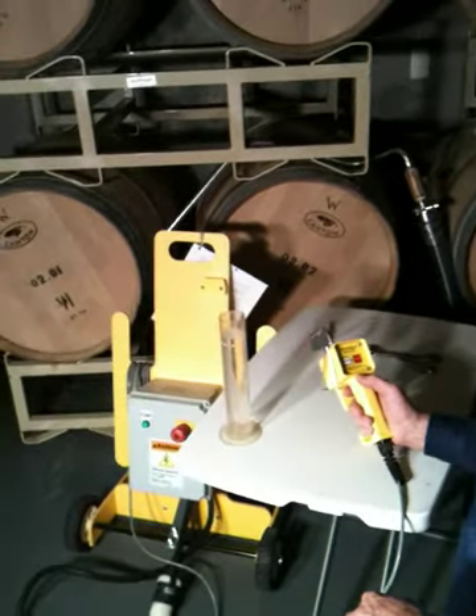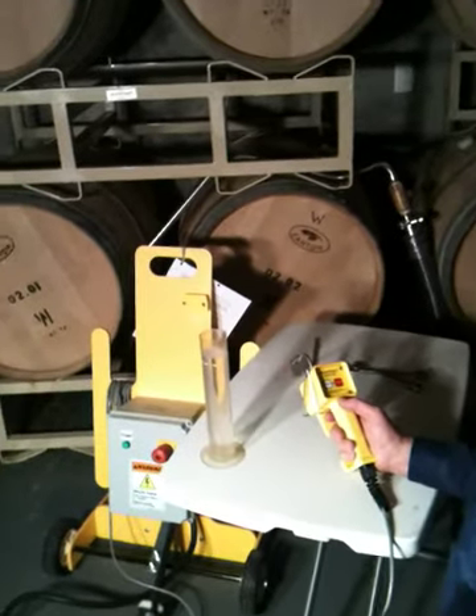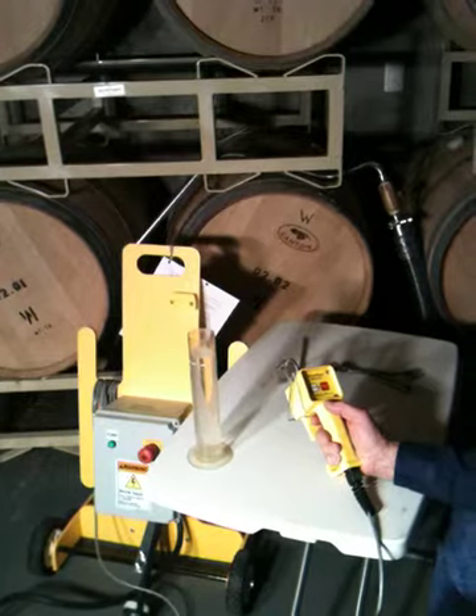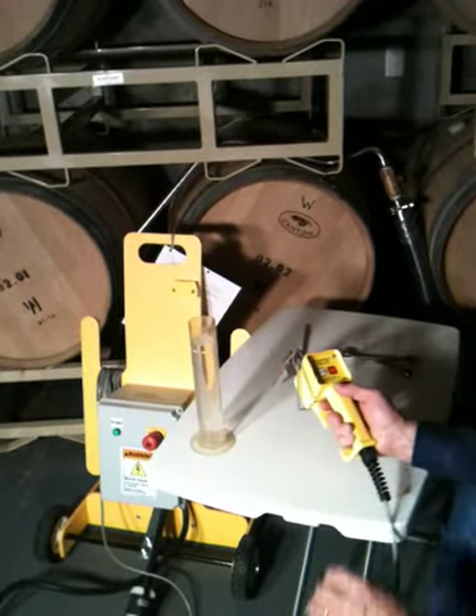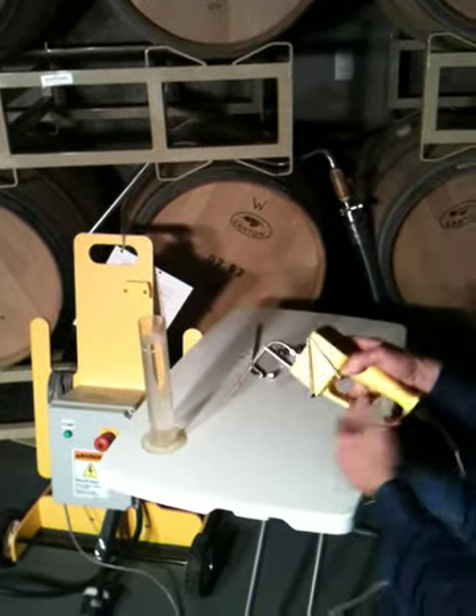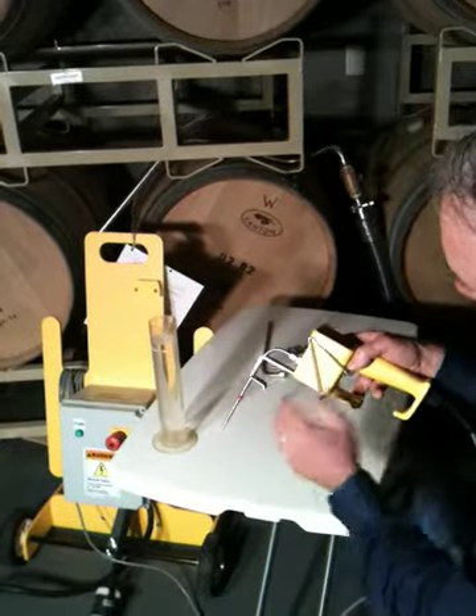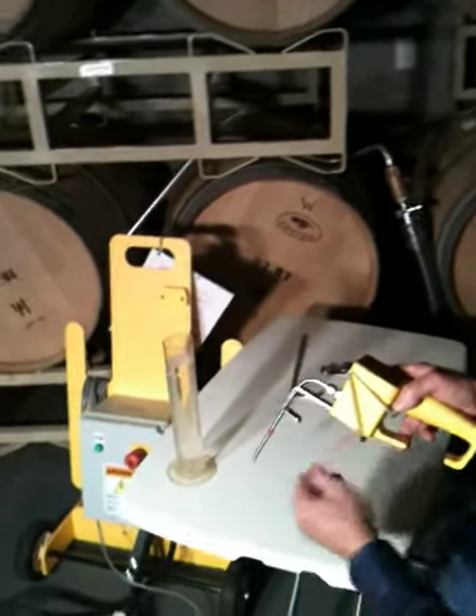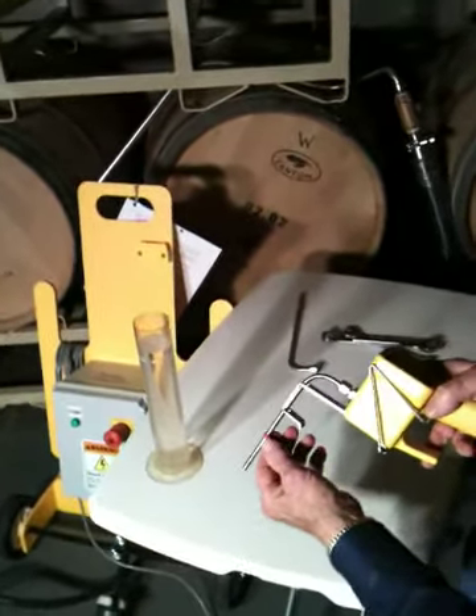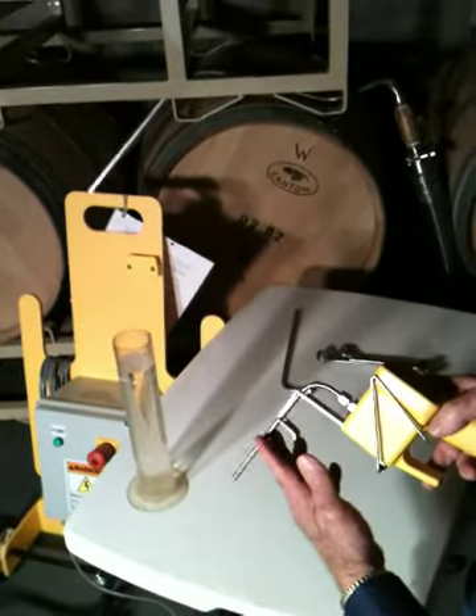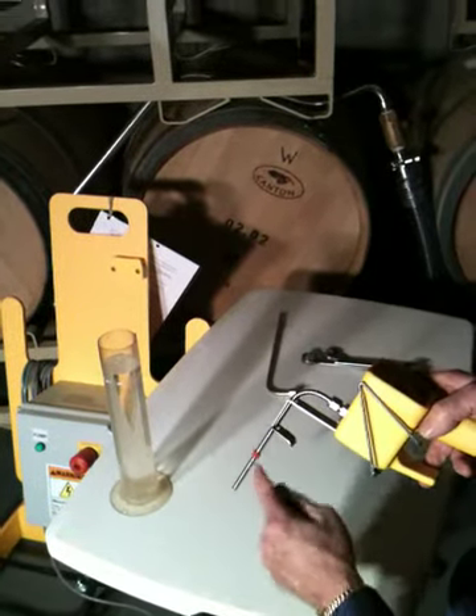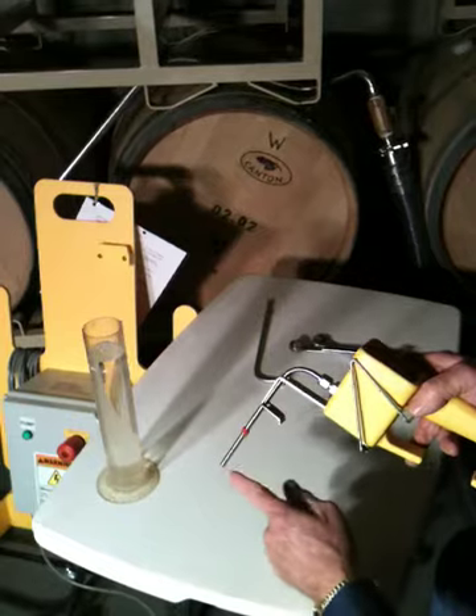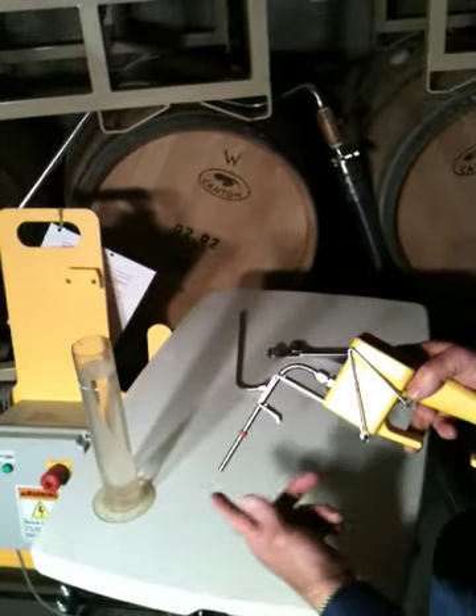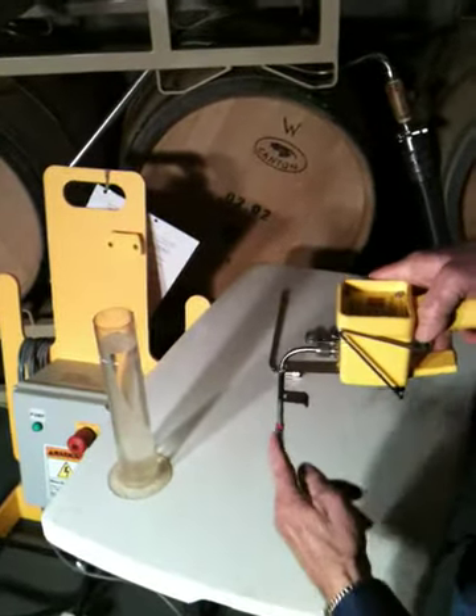This video is being produced to introduce the viewers to the calibration and leak testing of the Smartrack control system. This is using the handheld controller. This is a pressure sensing unit. The sensor is actually inside this handheld controller. This little red elastic band is used to demark or to give you an indication of where you want the level to shut off. So we've got it set in approximately 2 inches from the tip, measured vertically up.